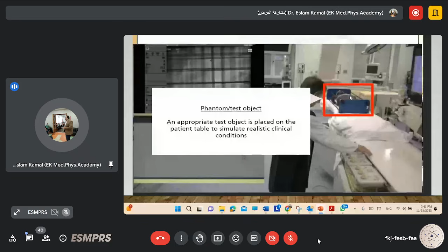So now we are going to move the patient close to the X-ray tube. As you can see here, the reading on the bottom left is going to be higher, reaching 750, 800, 852, 895, 937 microgray per second. Our dose rate is very high. So now it's around 900 microgray per second.